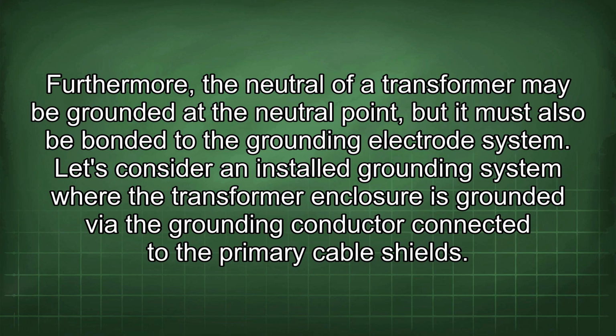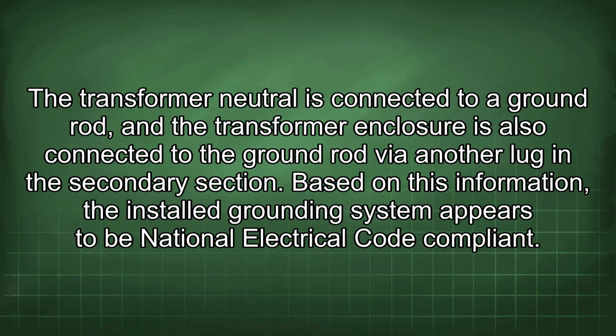Let's consider an installed grounding system where the transformer enclosure is grounded via the grounding conductor connected to the primary cable shields. The transformer neutral is connected to a ground rod, and the transformer enclosure is also connected to the ground rod via another lug in the secondary section. Based on this information, the installed grounding system appears to be National Electrical Code compliant.